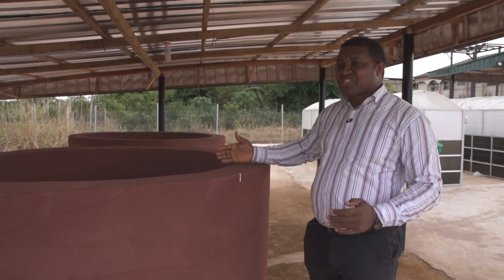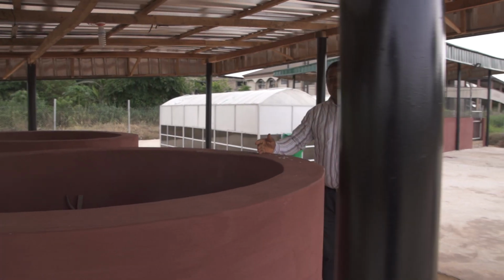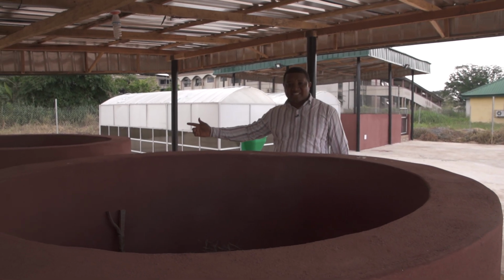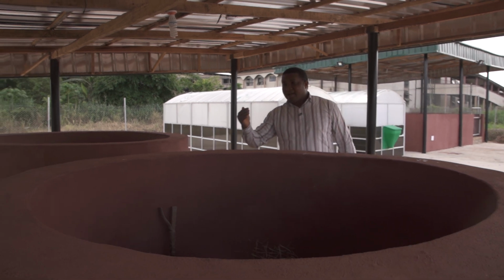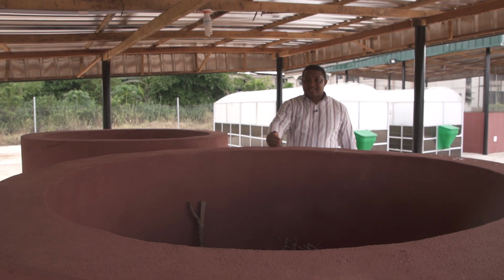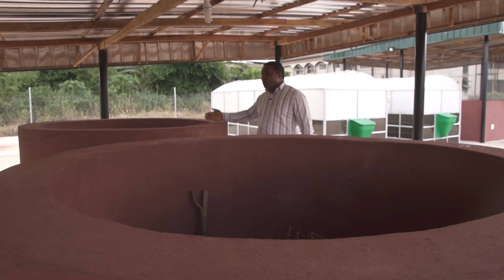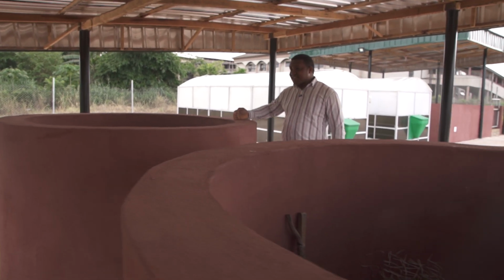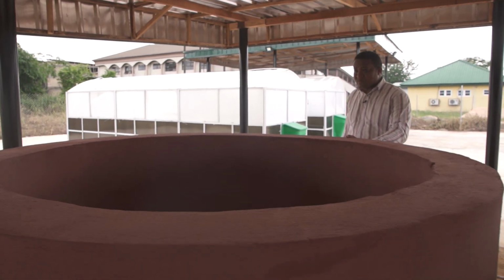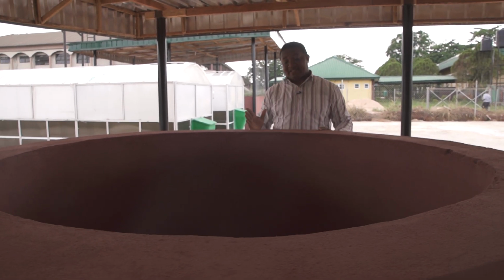When we've achieved that, we require a pump here to transfer the contents to the next tank, which we call the batching tank. Here, a calculated amount of feedstock is transferred from the mixing bay to the batching tank, and the batched quantity of this feedstock is transferred through a submersible pump by the positive displacement method.